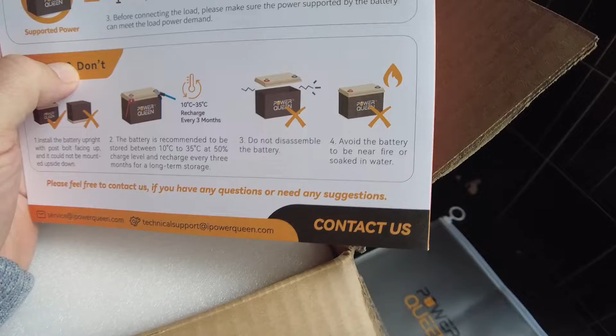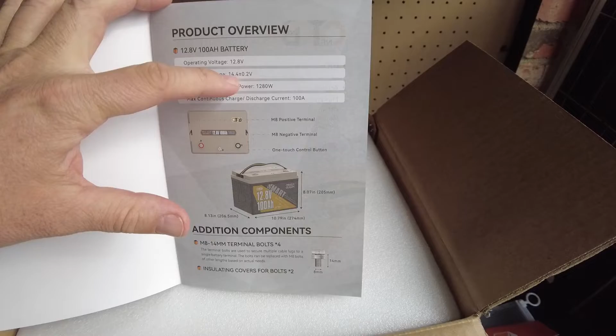So 12.8 volt, 100 amp hour smart version - this is what I was talking about. So this is a smart version, 100 amp BMS. The charging voltage is 14.4 plus 0.2, which is very common. We'll test that to make sure it actually gets to charge to that level. Max continuous load power is 1,280 watts, so basically 1C. Max continuous charge discharge current is 100 amps, which is again 1C. Has M8 terminals and one touch control button.